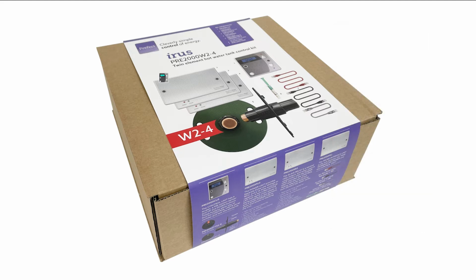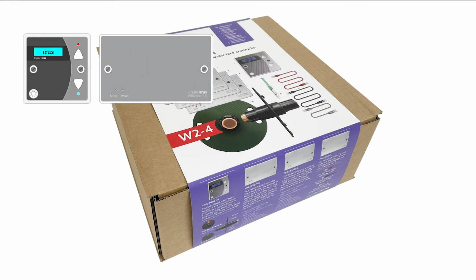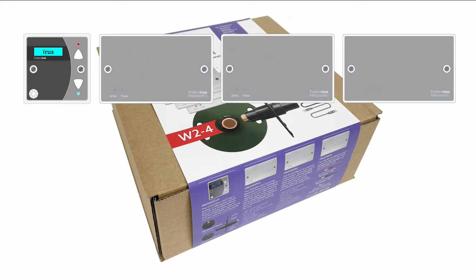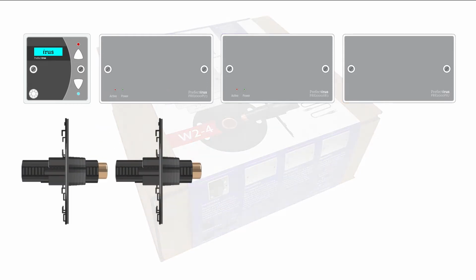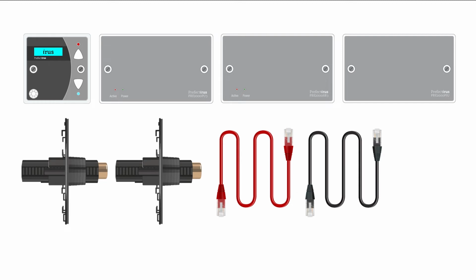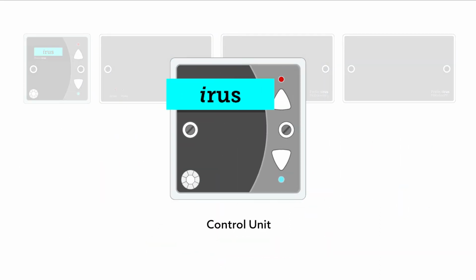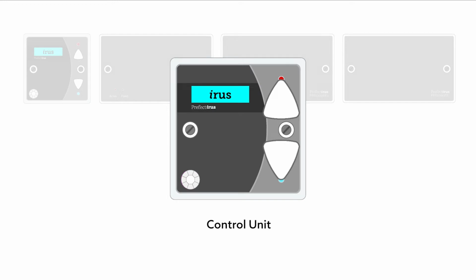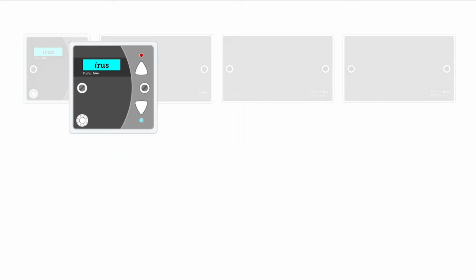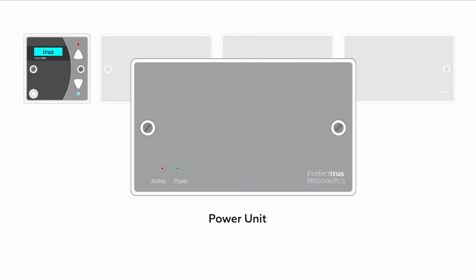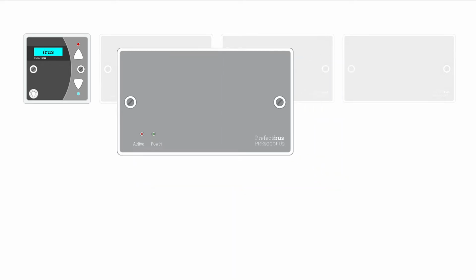The kit comprises the control unit, the power unit, the slave relay unit, the probe interface unit, tank probes upper and lower, 2 3-meter red and black patch leads, and 1 300mm patch lead, and thermal paste. The control unit has a screen, a PIR motion sensor, and up and down buttons. These buttons also enable you to find the control unit's serial number and test the elements. The power unit provides the control unit with separated extra low voltage, or SELV, and a 16 amp switching capacity. It has a red active LED that lights when the heater is drawing current, and a green power LED to show that power is reaching the unit.